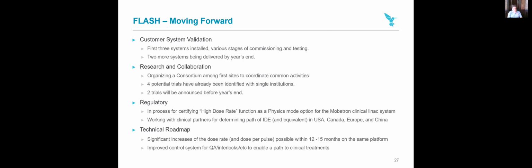Those first 2 trials will be the CHUV and Lausanne, and I think others will come out very shortly behind that. We're in process of certifying our high dose rate mode functionality, and it operates in physics mode, so it's not clinical. It's not a clinical mode. You can't mistake it and use it on the clinical system at all. It's impossible to do that. You have to physically plug in the flash controller, flick the switches, and intentionally go into physics mode, which has a password. So you do have to get into physics mode, and that's being certified now. We're working with the countries mentioned here to get an IDE, or an equivalent in those countries, so that our clinical partners can begin doing experiments with humans. Right now, you don't need an IDE for animals.